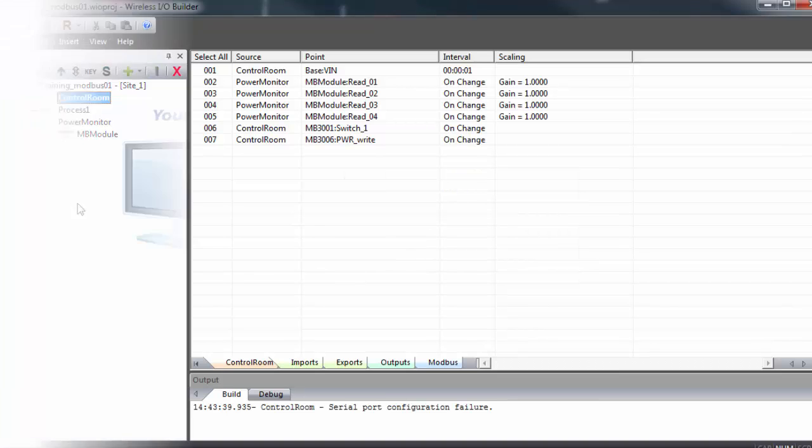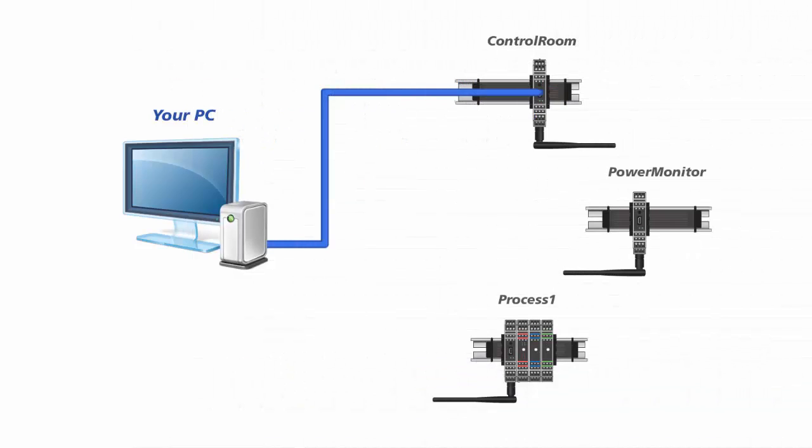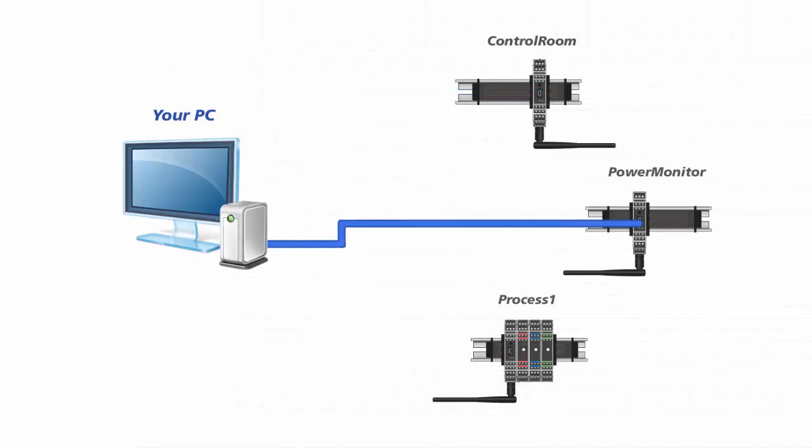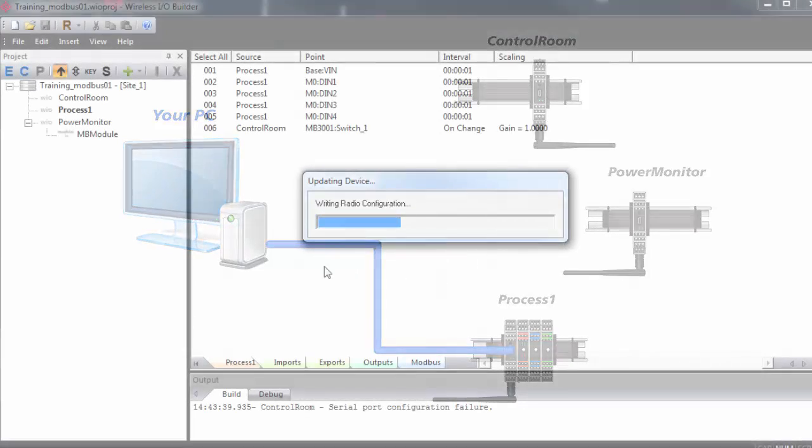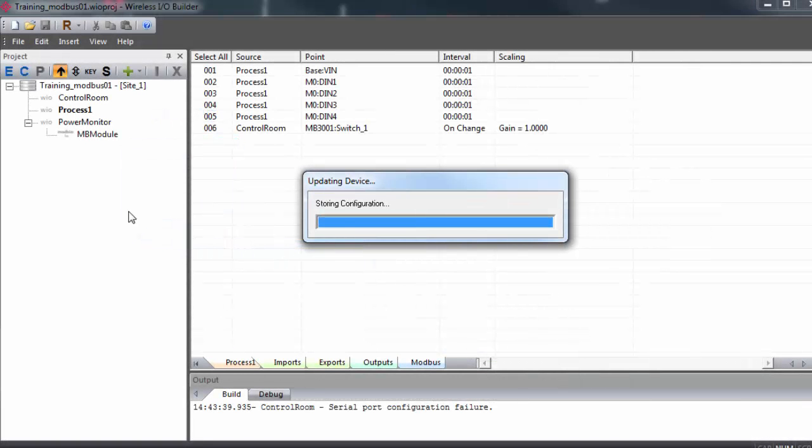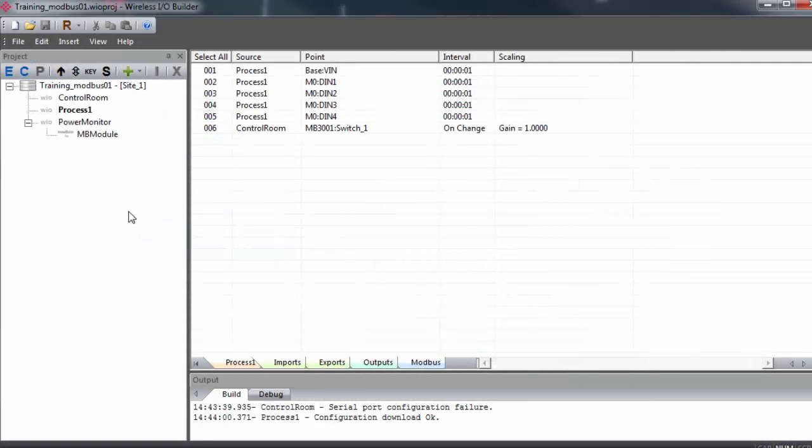And when this is done, we'll have to plug into each of the other gateways, making sure that they are selected in the tree view and update them as well. Anytime you make changes to the communication parameters or the mapping of points on a gateway, you're going to have to plug in and update the configuration.